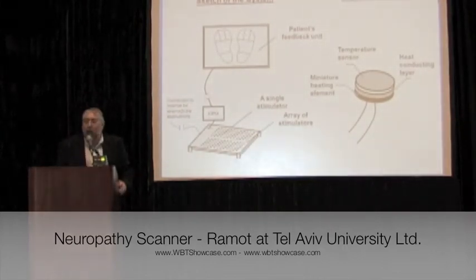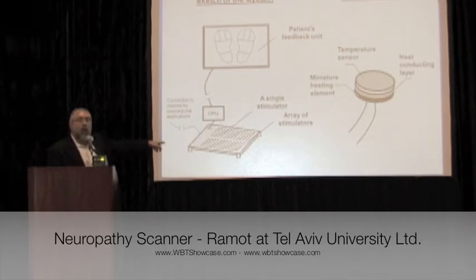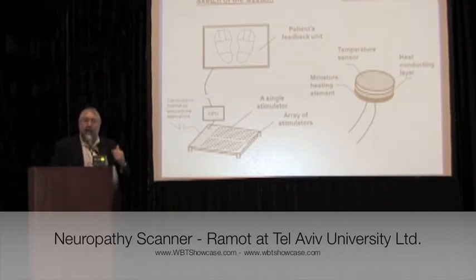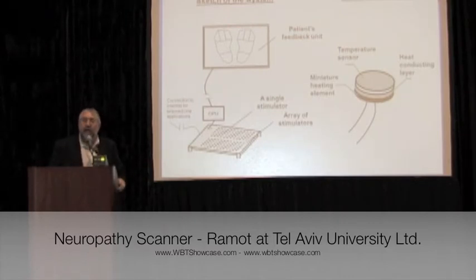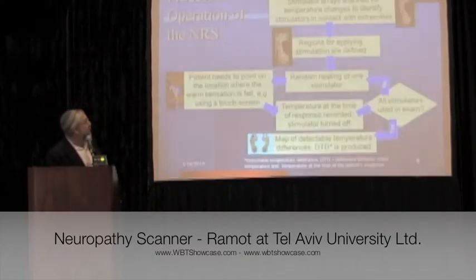So the idea that we have, and we are planning to build, is an automatic detector where the patient will stand on an array of sensors. The combined sensor and heat element, and randomly he will be exposed to heat underneath areas of his feet. He will then be in front of a touch screen, and he will touch the area of the foot where he felt the heat if he did so. And this way, automatically and without intervention of a podiatrist, you can then map and follow up on what's happening with the neuropathy in these types of patients.